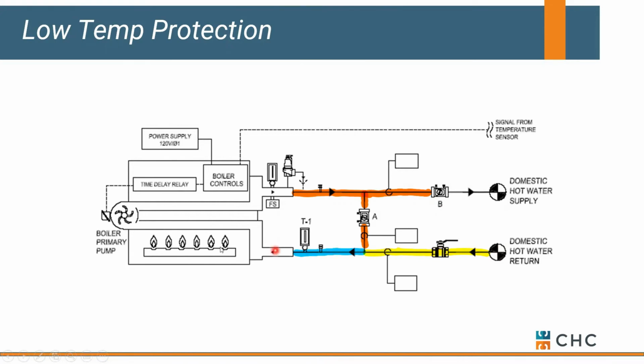If it comes into our boiler and leaves warm, how are we going to get this above 130? We can add some circuit setters, basically calibrated ball valves, and by choking down on our circuit setter B, we create some resistance and force that hot water back into our return, okay? So we're going to choke circuit setter B until temperatures over here on our return get above 130. Basically, we're constantly bypassing some of our hot water back into the return with the goal of keeping this above condensing mode. So this works really good when your return water temperatures are constant, and you do that off of a domestic storage tank. So this would be more a water heater than a boiler. I'll get to that in just a second.